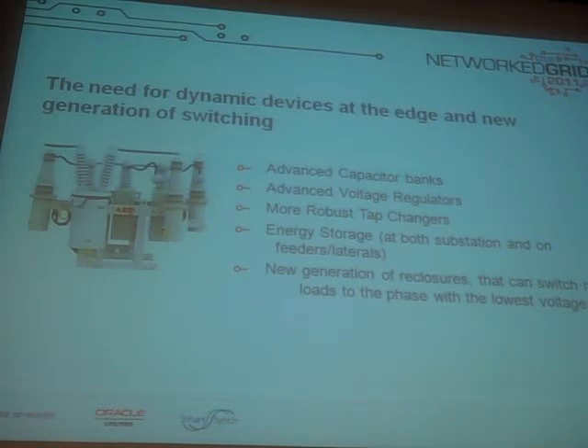Apart from cap banks and voltage regulators, tap changers become another really important technology, which today you really can't alter more than 2 or 3 times at the most, because they're just not designed for that kind of use. So a whole new generation of tap changers needs to be born, so that you can alter the voltage at the substation to affect the voltage at the endpoint. Today, a lot of substations might have one tap changer serving 4 to 6 feeders. Ultimately, we're going to get to a point where we need 1 tap changer on every feeder. It all speaks to a bigger and bigger market for these DA solutions.